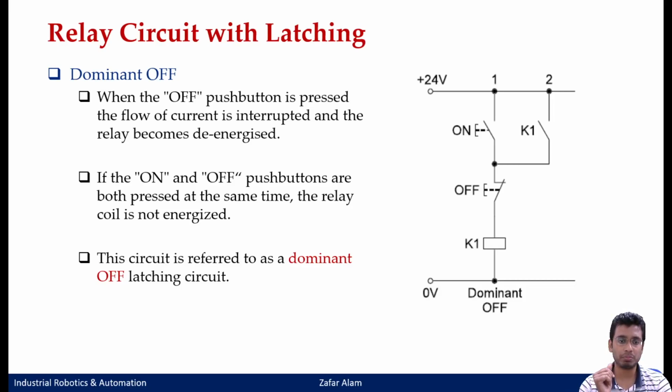But in this case, what is happening? The moment you press the push button, even if you release it, this K1 acts like a latch, and hence this push button behaves like a switch. Just like a detent switch maintains its position, this relay will continuously have the supply and maintain its position until I switch it off using some other push button. In this case, it is known as your off push button.